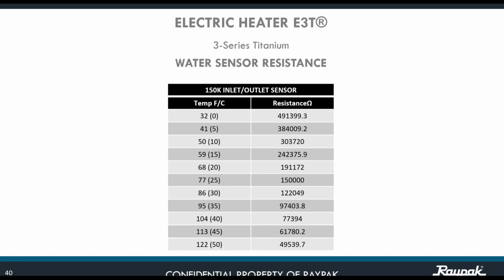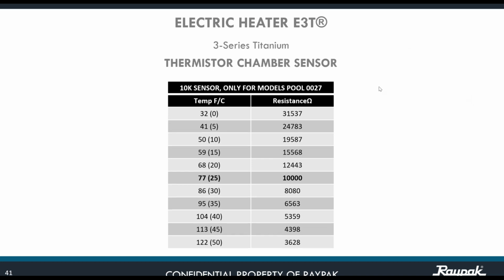Also, you can check the water sensor resistance. That is 150K for the inlet and outlet sensor. All you need to do is know the temperature in the pool and the resistance. And how do you get the resistance number? You connect your meter, and you get a reading based on the temperature of the water. For the thermistor chamber sensor, remember that this is only for the 27 kilowatt. There is also the same test. For a specific temperature, you're going to have a reading in ohms on those particular sensors for the 10K sensor.